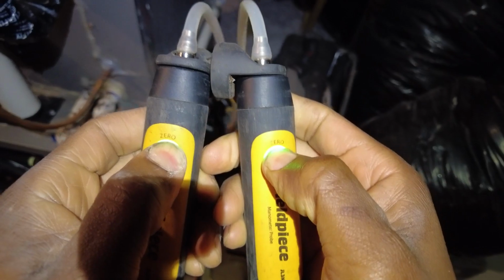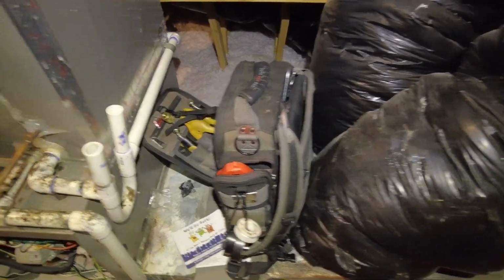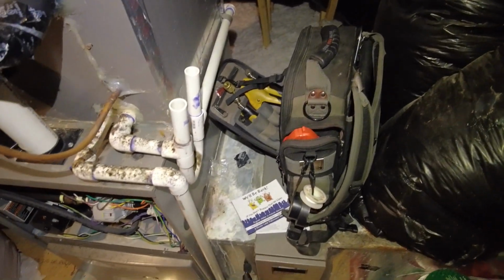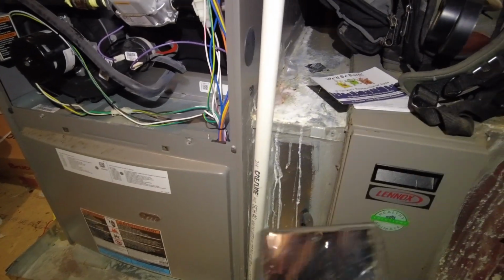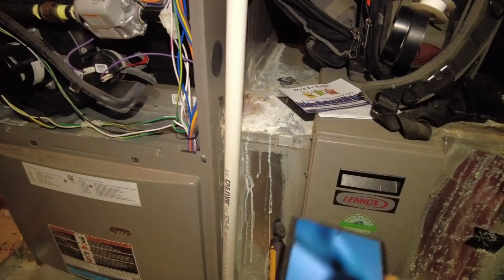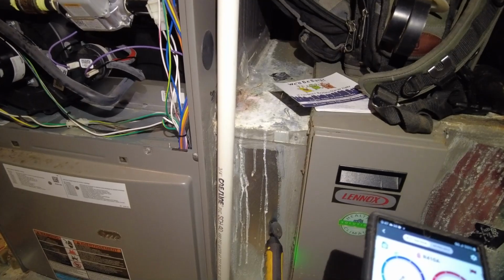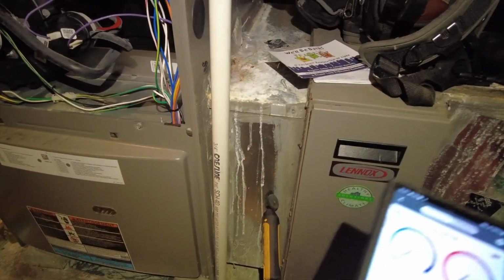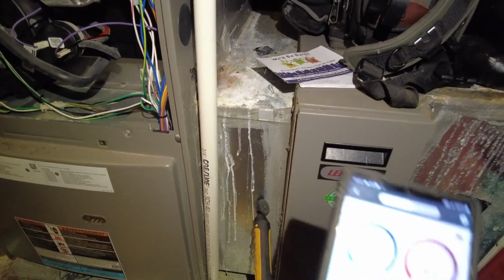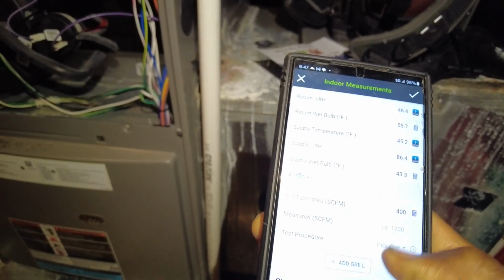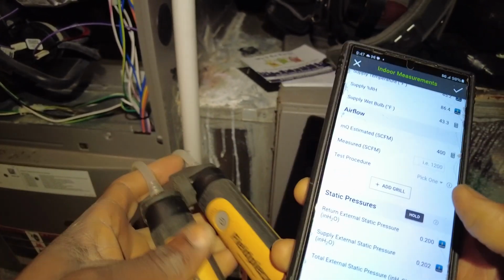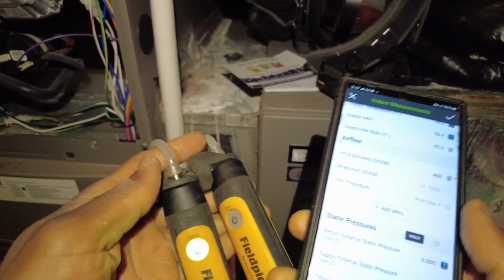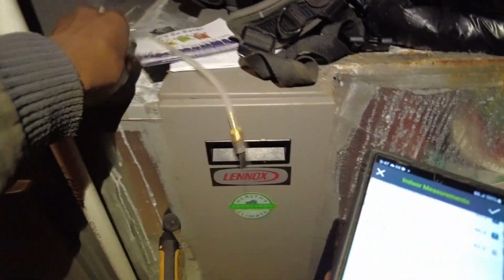with one zone, especially the downstairs zone, closed, because heating mode is going to run less airflow. So the way you want to set up a zone system, if your downstairs thermostat closes down and the static pressure is still okay, you should be fine to not even use a barometric damper, because once you throw that thing in heating mode, it's going to have less airflow, and essentially the upstairs is going to be the one that's closing more prominently. So not to say it won't close at all downstairs, but it's going to be more biased toward your upstairs, if that makes sense. So we're just going to check our total static and see what we're working with here.